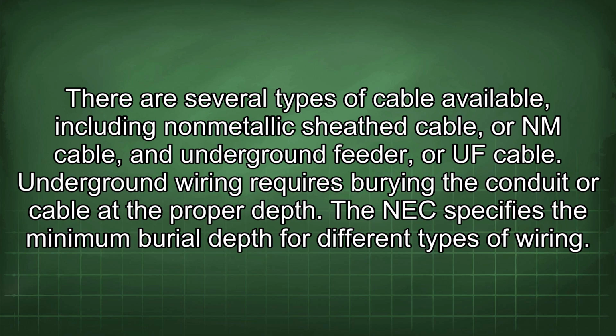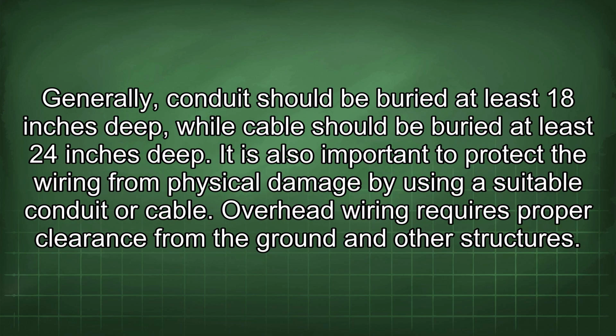Underground wiring requires burying the conduit or cable at the proper depth. The NEC specifies the minimum burial depth for different types of wiring. Generally, conduit should be buried at least 18 inches deep, while cable should be buried at least 24 inches deep. It is also important to protect the wiring from physical damage by using a suitable conduit or cable.